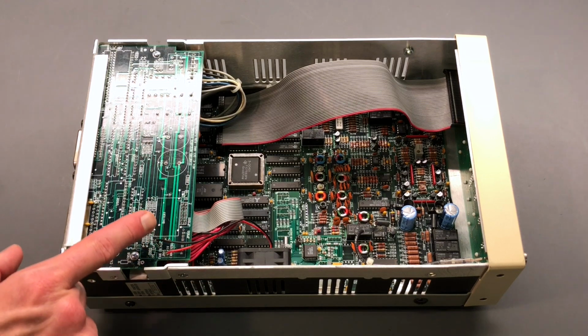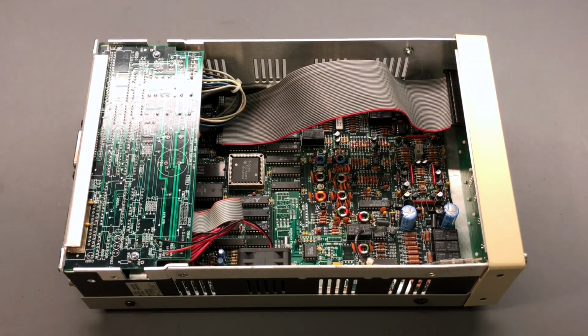Now, if this battery has become weak or is dead, the RAM won't hold up when the instrument is turned off. Now, here's why the RAM comes into play. The calibration factors, or cal bytes, may need to be changed. So what happens is, when the instrument is powered up, if the RAM is corrupted or is empty, it will move a copy of the data from ROM over to RAM. It should be held in RAM, and then you can change the data that's in the RAM as needed if the instrument needs to be calibrated.